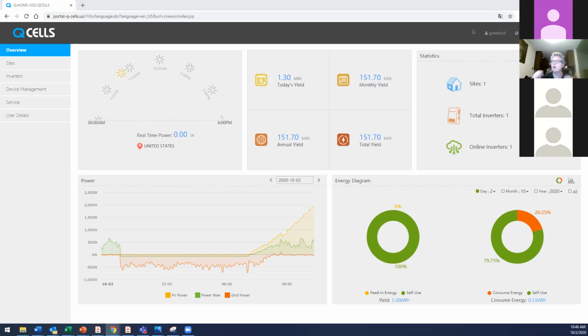Another question from Anonymous: can I hook my air conditioner and laundry machines up to this? Pay attention in the data sheets to the maximum output current depending on the number of batteries connected. You have a much greater chance of installing on larger loads when using the 3-battery setup. But check the placard on the back of each device for amps, volts, and watts it will pull, and make sure you don't overload the backup load panel, because that will trip the inverter.